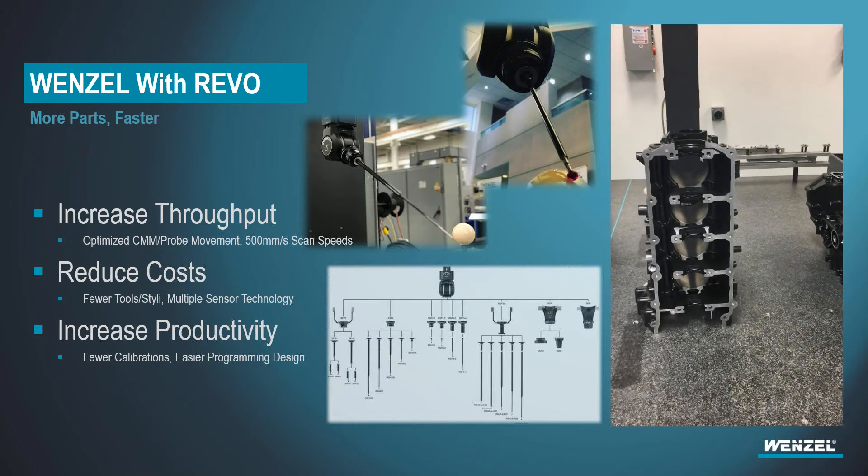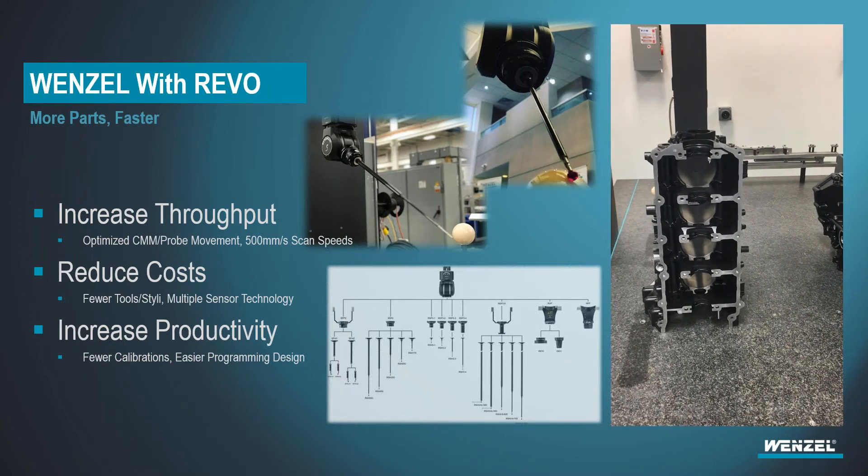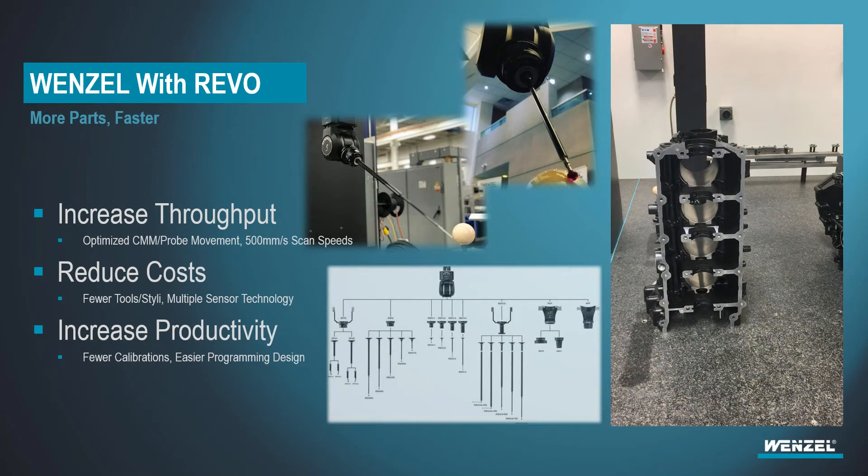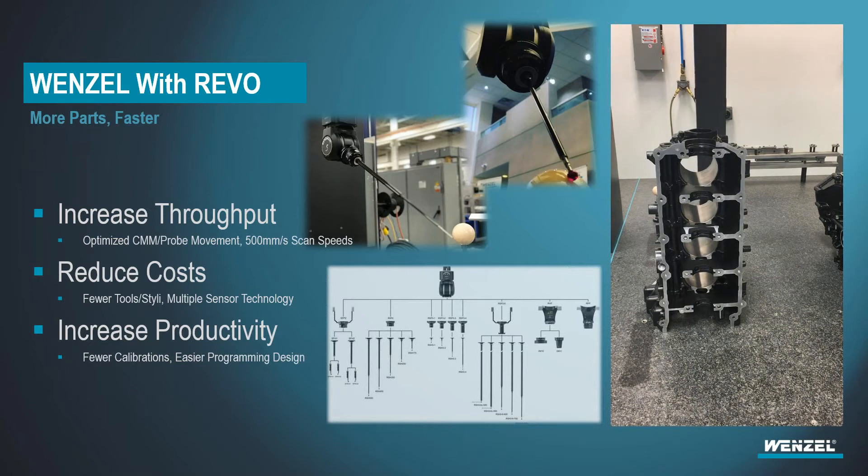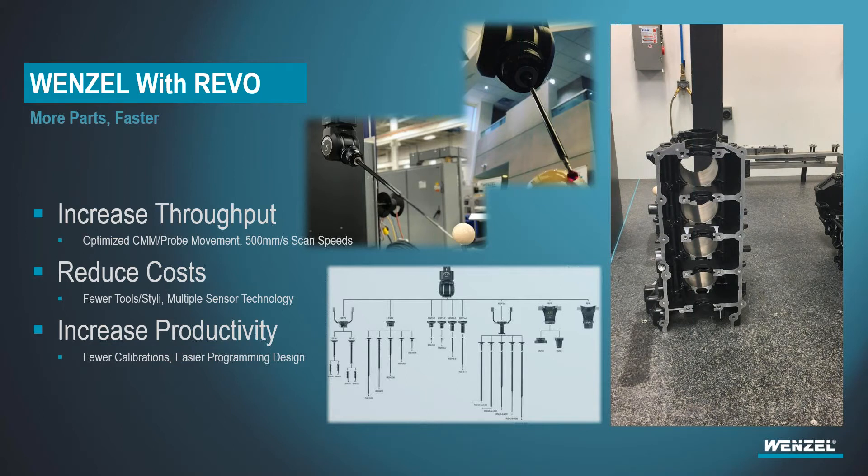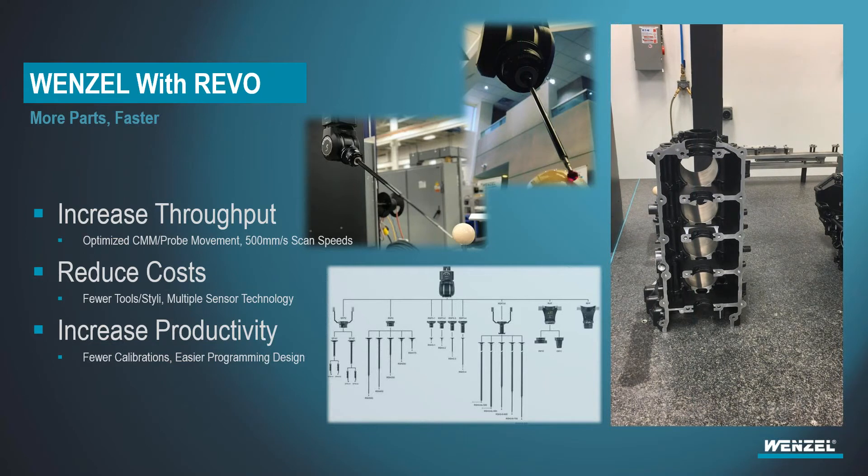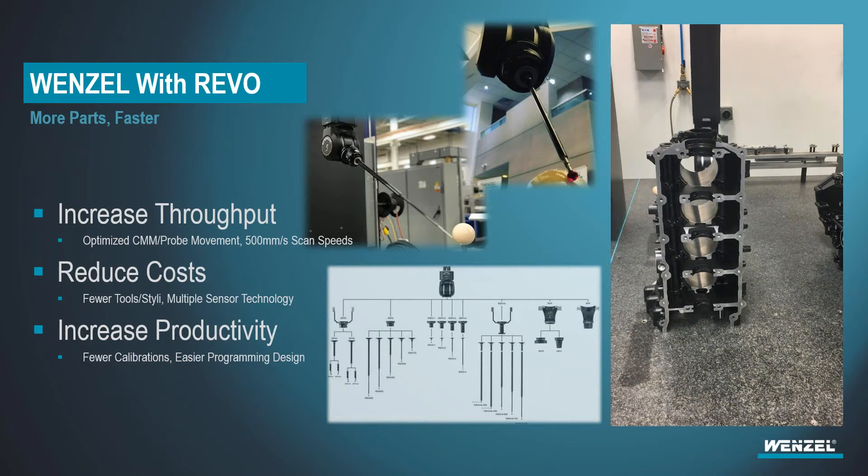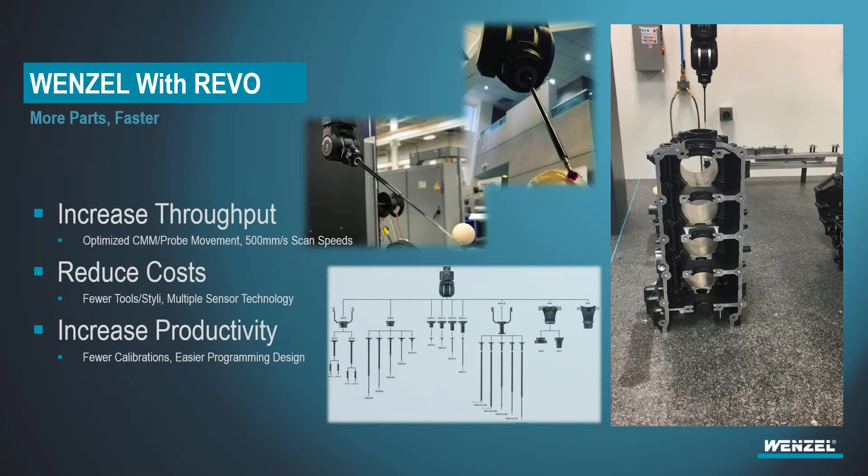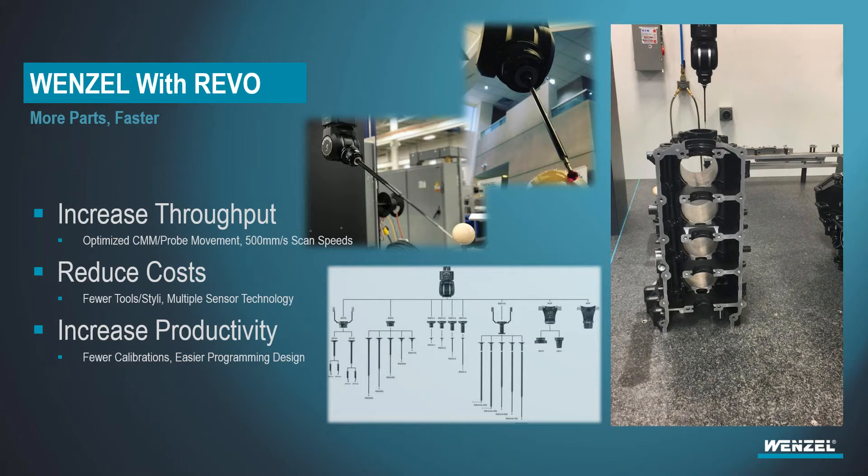A lot of times we get in trouble because the parts take a lot longer to measure than they take to machine. Certainly in a lot of cases, maybe not so much with blades and blisks, but certainly with engine blocks and that type of part. And the REVO allows the inspection to keep up with what's happening on the actual shop floor here. Another benefit of the five-axis system is typically as you're looking at complex multiple angles for your scans or for the inspection of your parts, calibration becomes a big issue. If you have multiple racks set up for all your different angled probing, different styli sizes, and different reach probes, you really can cut that down with the REVO system.